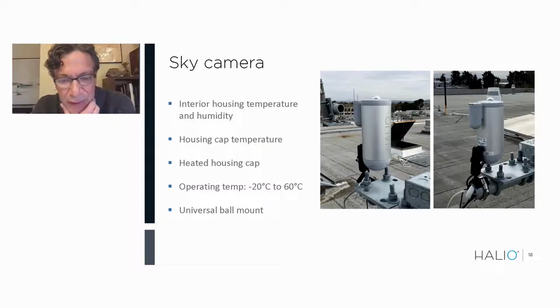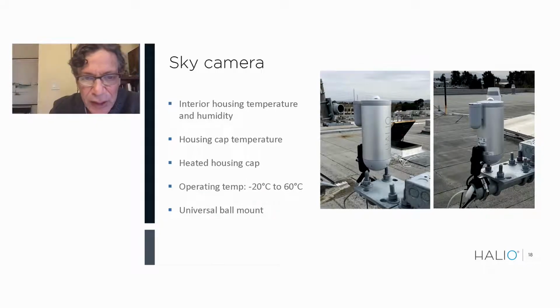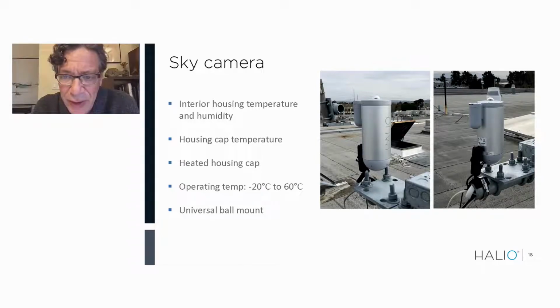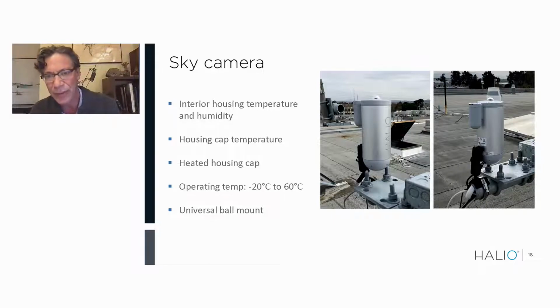To control for and protect from environmental conditions, the Sky Camera includes several onboard systems, including interior housing and temperature and humidity sensors. There's a housing cap temperature sensor using a thermistor, and we use that information to trigger a heater that's attached to the housing cap. So if it's a snow condition, then we can heat the cap and melt the snow and not allow the snow to accumulate over the camera sensor or the illuminance sensor. There's also a universal ball mount that allows variations of mounting options on any roof structure or appendage.